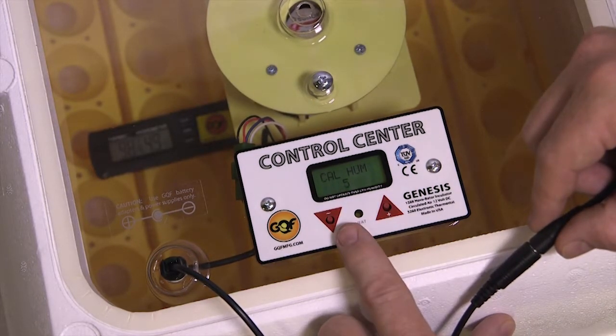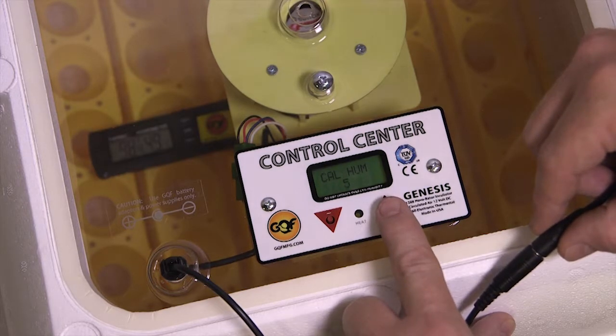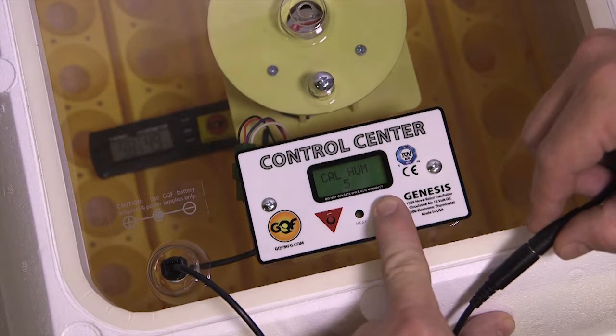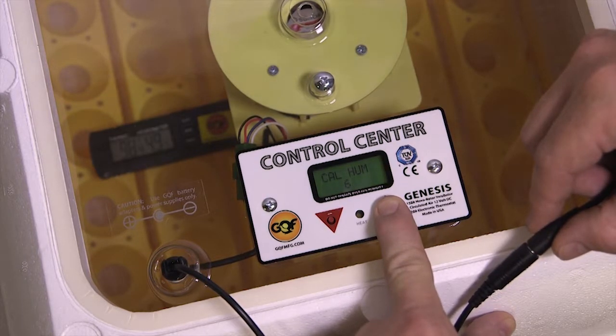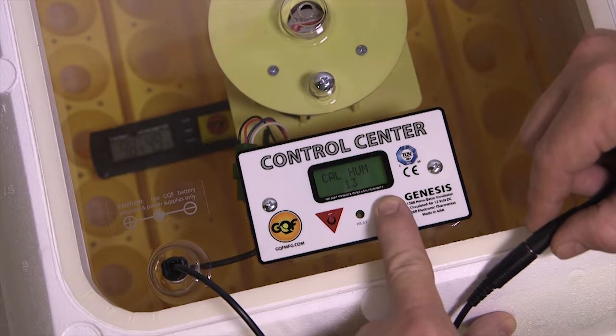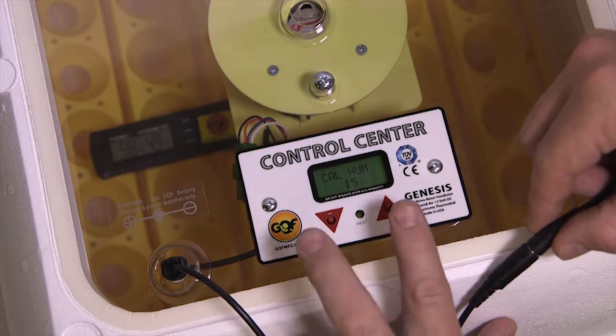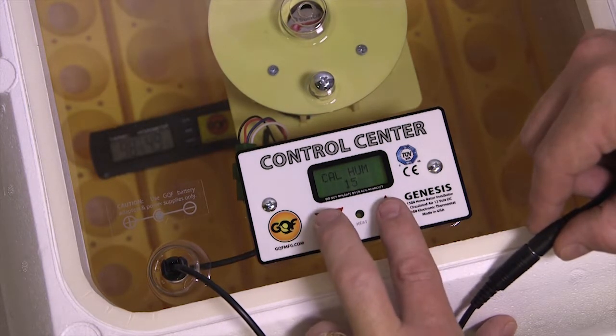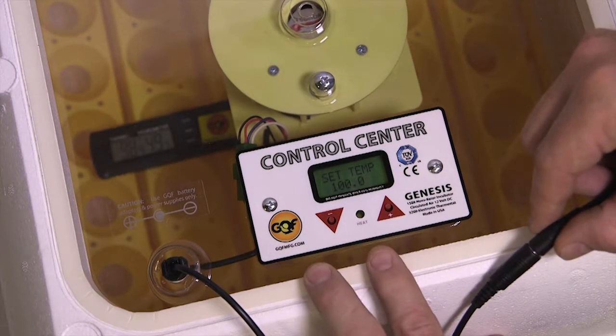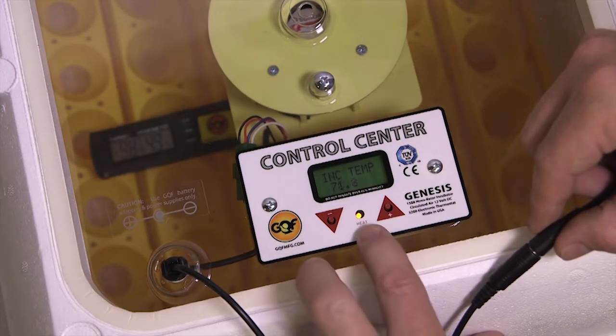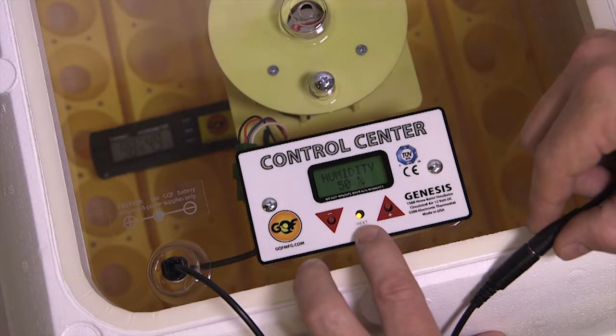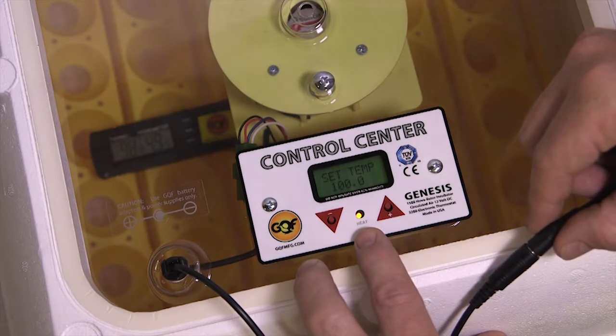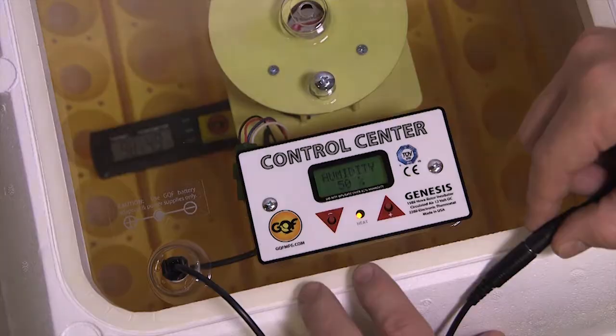And when I release, it says cal humidity. And so I was about 10% low, so I'm going to add 10% to the control center by holding the up button. Now, when I press both buttons and release, we'll go back to the original screen and notice the heat comes back on because it's adding that temperature. And we just need to wait about 30 minutes for this thing to regulate.